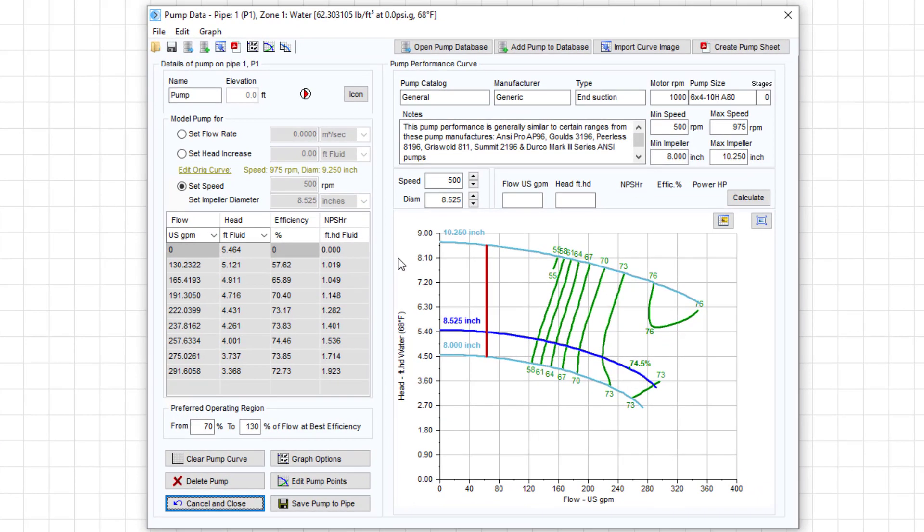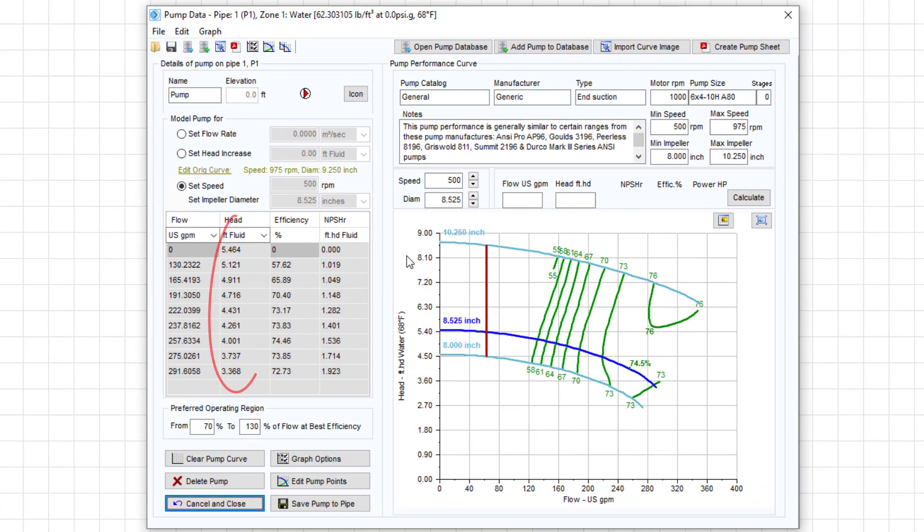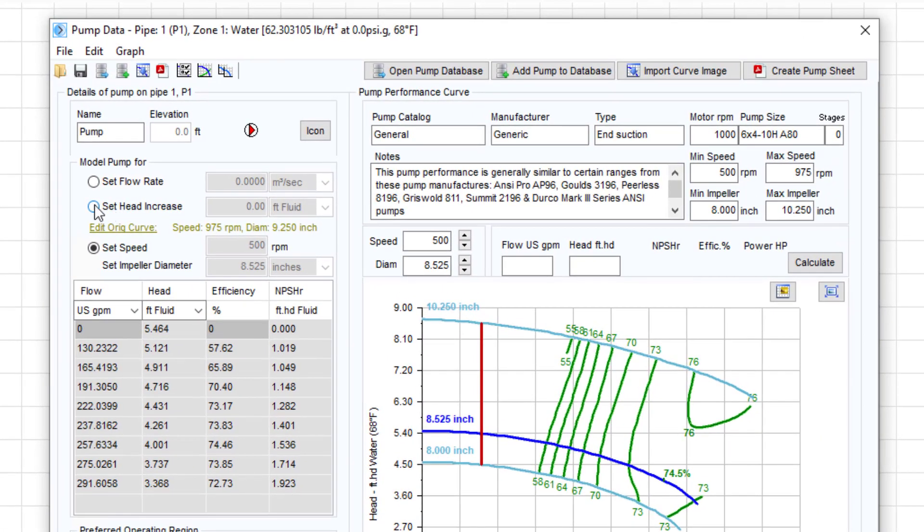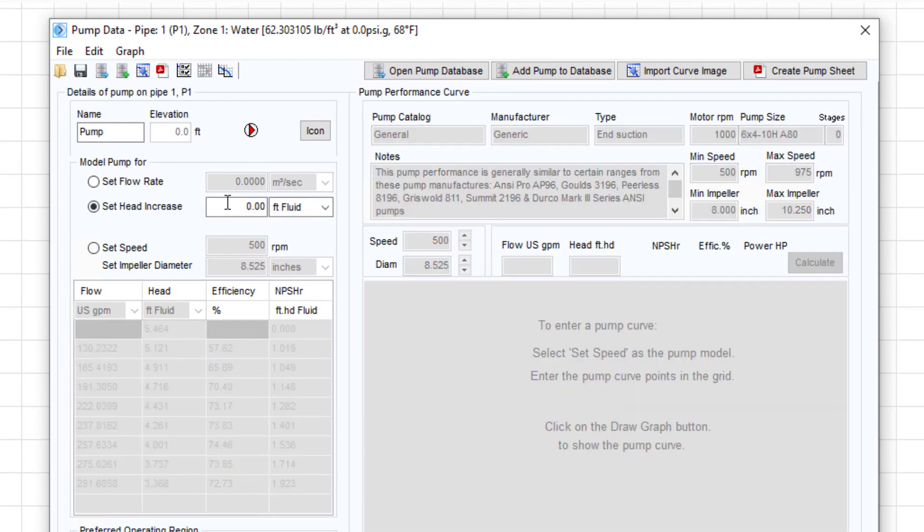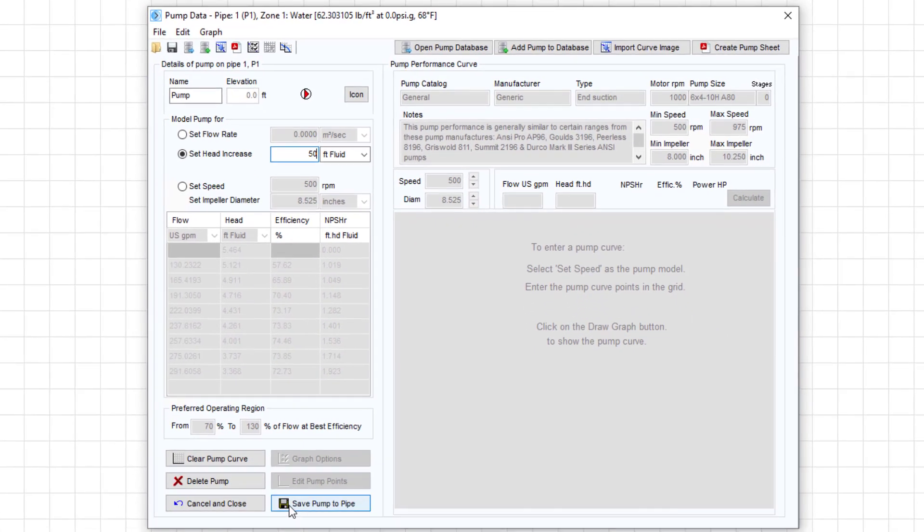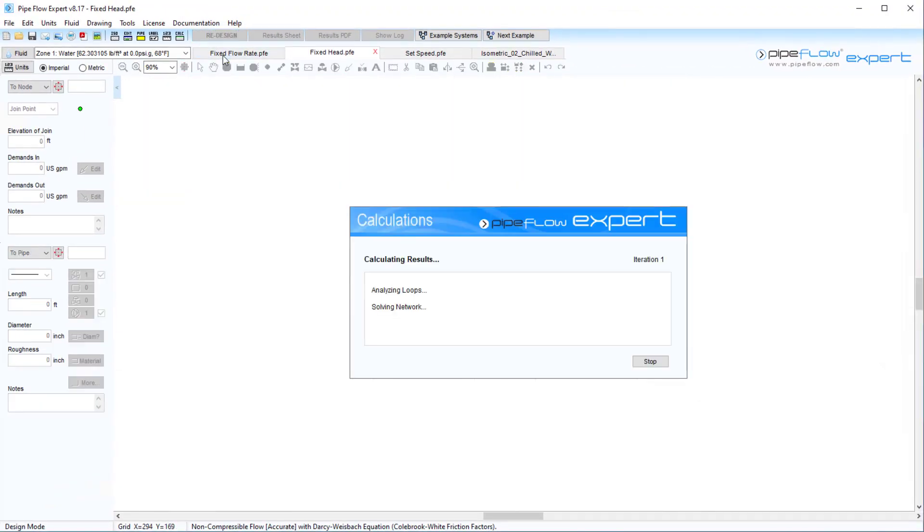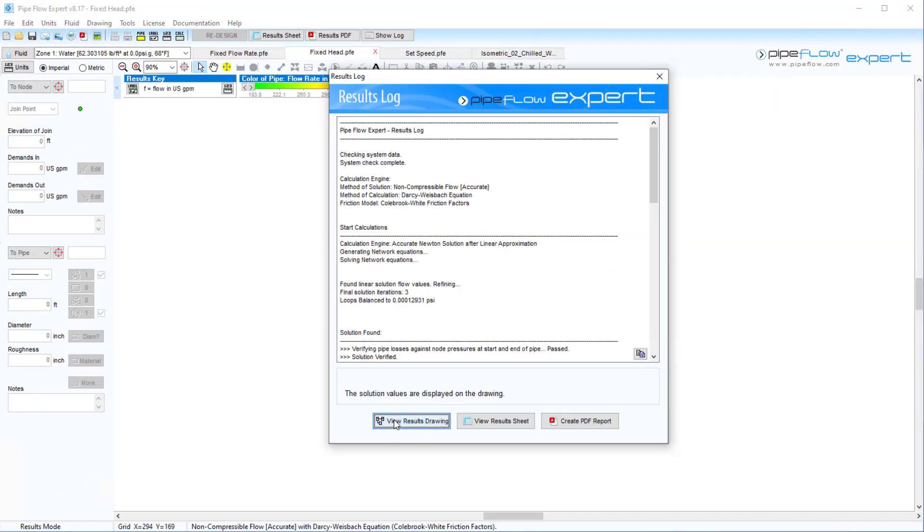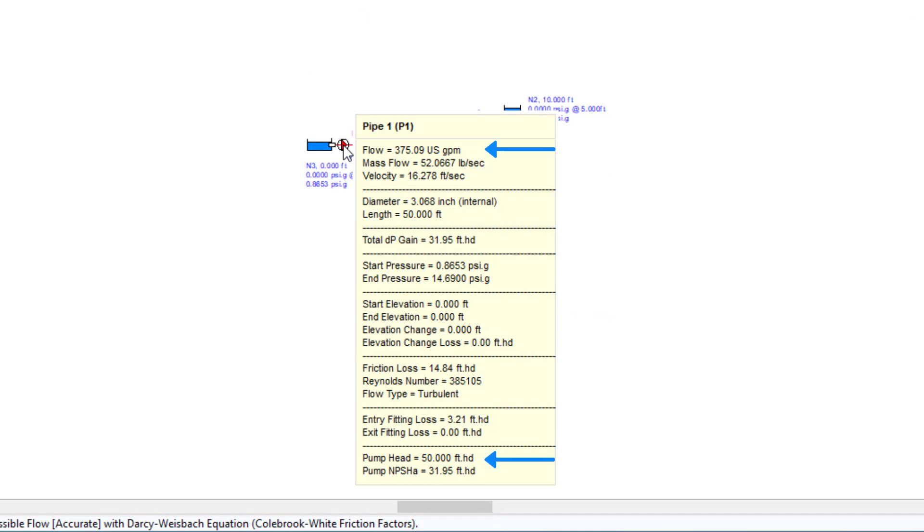Using a fixed head increase can be useful when troubleshooting your system. For example, you may solve your model and realise that the pump you have added does not produce enough head to meet the requirements of the model. You could then set a pump to a large fixed head value and then gradually reduce this until the requirements are met. The software will then report the flow rate produced for the amount of head specified and this data can be used to select a more appropriate pump.